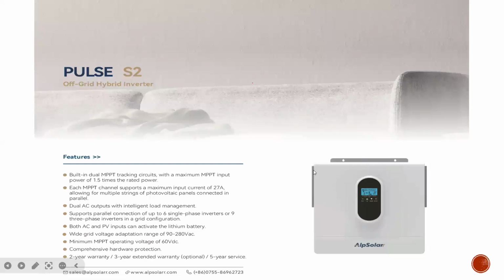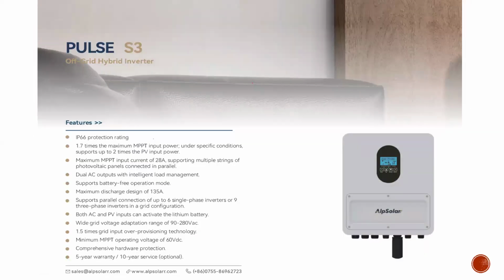And the next thing I would like to talk about here is the communication. It has RS-232 communication protocol, RS-485, CAN, dry contact, and your external battery NTC, which is negative temperature coefficient. All of these communication protocols give you the assurance that this inverter is well compatible with a wide range of lithium batteries out there. At the end of this session, you're going to see a list of batteries, which is not exhaustive, right? A list of batteries that this inverter, all of our inverters, are actually compatible with.